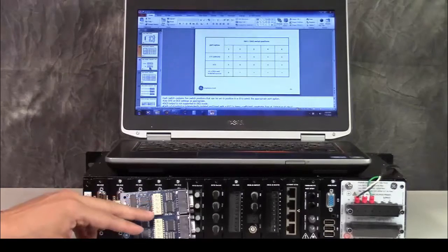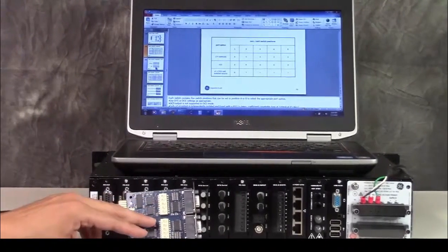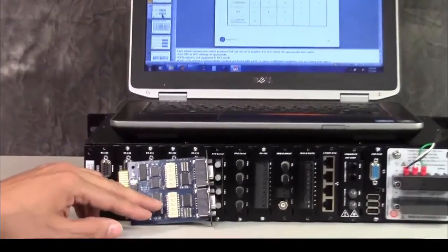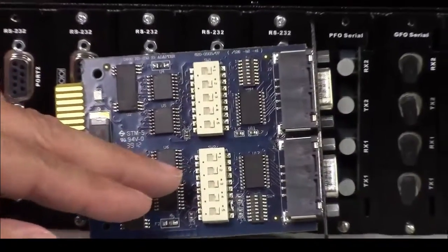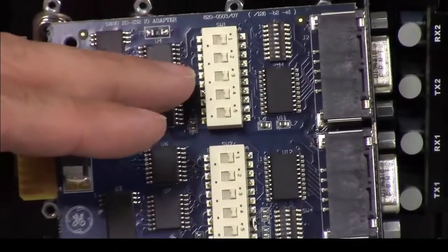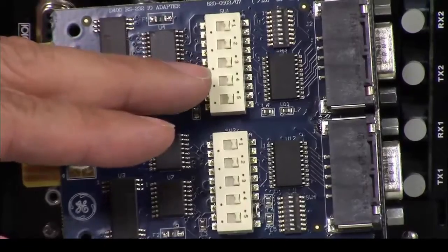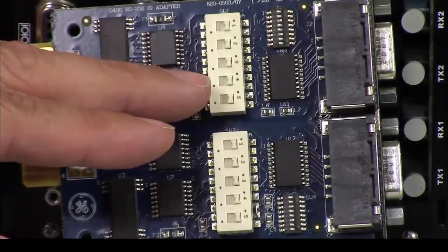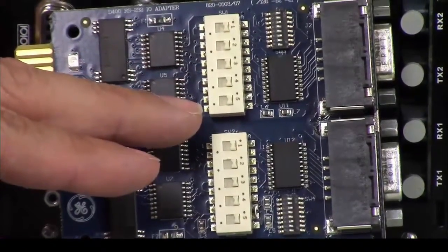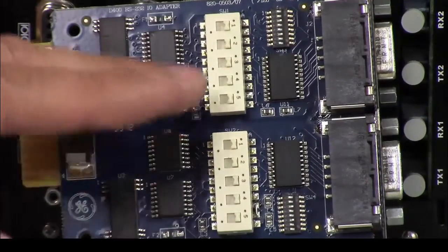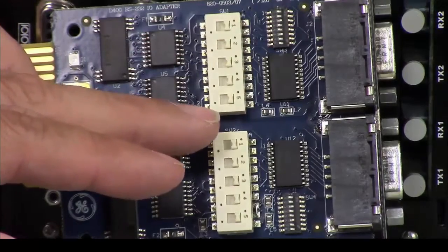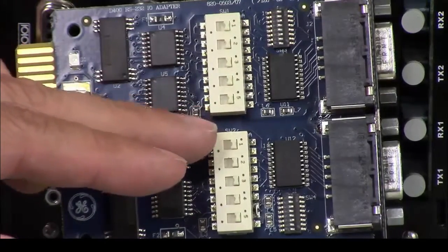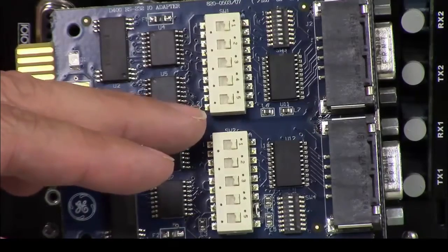Okay, so we've got a DCE and a DTE device when we want to communicate on a serial port. A DTE device is a terminal device or a data terminal device, and a DCE device is a device that sits between the data terminal, so it's like a modem, right? So a communication device like a modem. So basically, if we want to set it for a DTE device, like if you're connecting this directly to a relay in the field, you would use a null modem cable.